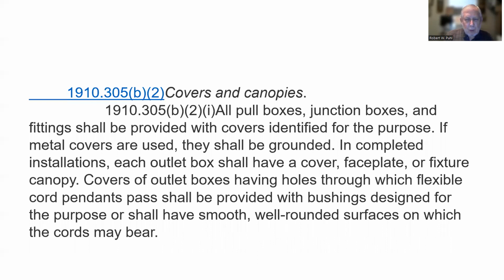Covers and canopies. All pull boxes, junction boxes, and fittings shall be provided with covers identified for the purpose. If metal covers are used, they shall be grounded. In completed installations, each outlet box shall have a cover, faceplate, or fixture canopy. Covers of outlet boxes having holes through which flexible cord pendants pass shall be provided with bushings designed for the purpose, or shall have smooth, well-rounded surfaces on which the cords may bear.